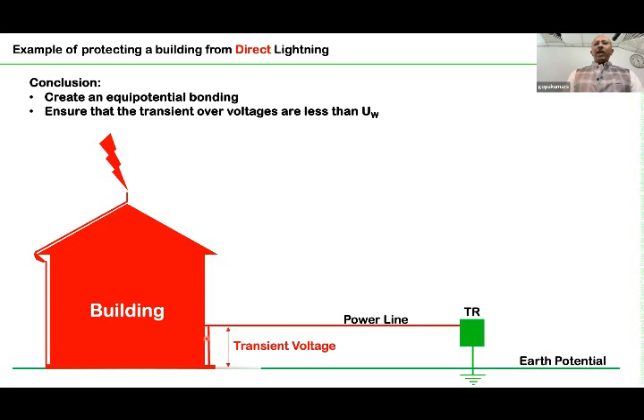People always ask, then what will happen? The lightning current will take a path. It will go through the power line. To some extent, it will pass through the power line. It may destroy your neighbor's building. People always ask, if I put in an SPD, the lightning current is diverted. As a result, the neighbor's building will burn.